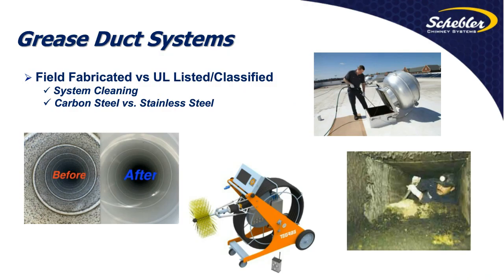From a cleaning standpoint, the method that seems to be most prevalent today to cleaning a grease duct system is not the guy in the right-hand corner with the scraper cleaning out the duct system. What we see most common today is coming in with a pressure wash system, either a wand type system, opening access doors or through the termination, or there's a mechanical device nowadays, as you see down there, with a brush, applying a cleaning solution that would be basically snaked through the ductwork to do the cleaning. It's much easier to obtain a good system cleaning with a round duct that's constructed of stainless steel than to try to get in there and thoroughly clean out the corners and change of direction of a rectangular ductwork.